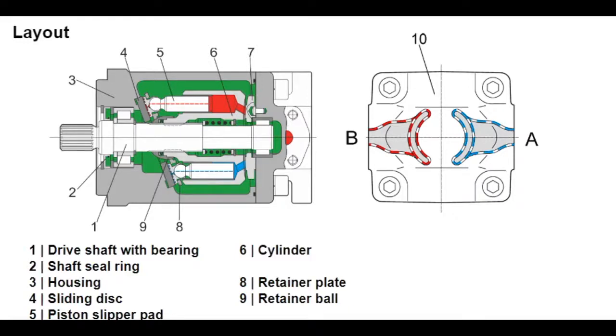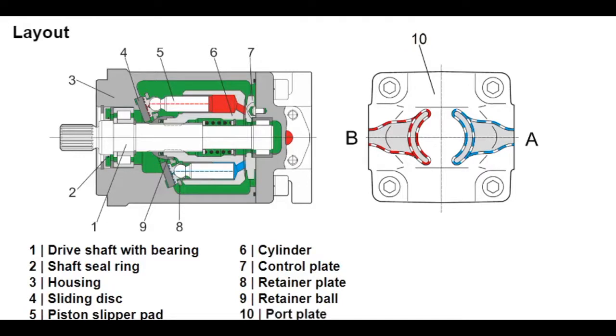The forces at work in the hydraulic section of the rotary group — that is, the cylinder with pistons and control plate (7) — are in equilibrium. The principle of the spherical control surface, its lubrication, the pre-charge pressure of the cylinder with springs, etc., is comparable to the function of the bent axis rotary group. The port plate (10) contains the pressure ports A and B. Depending on the flow direction, the motor rotates clockwise or counterclockwise.